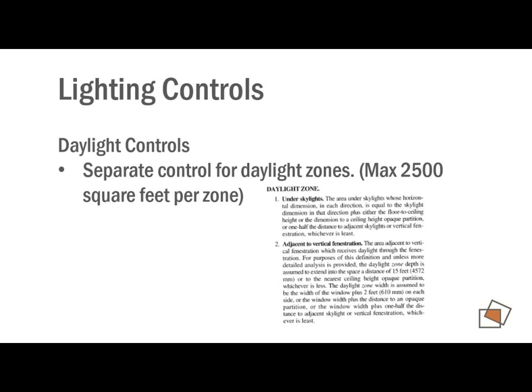There's an area under the skylights, any area just under the skylight, and then any area that's adjacent to a window, for fenestration. So pretty much from the top of the window, you draw an angle down, and then 2 feet past the edge of the window, that would be a daylight zone. So if you had a fixture in that zone, 2 fixtures in that zone, they have to have their own control.